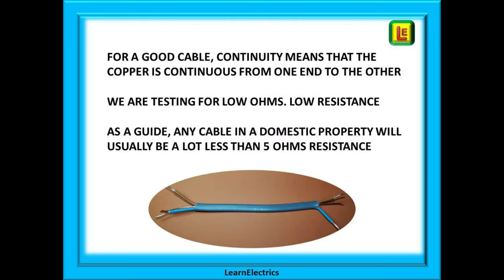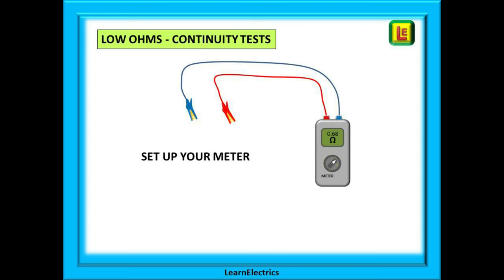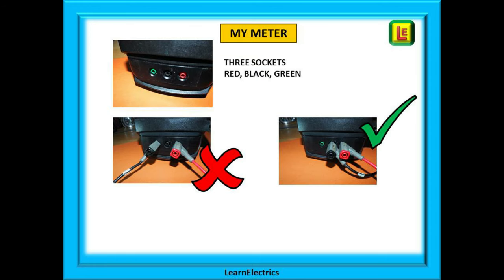For a good cable, continuity means that the copper is continuous from one end to the other. We are testing for low ohms, low resistance, and as a guide any cable in a domestic property will usually be a lot less than 5 ohms in resistance. The first step, always before doing any testing, is to set up your test meter and to make sure that it is functioning correctly. Different manufacturers make their meters with slight differences, but if you learn how to set up your own meter correctly then it is very easy to adjust to someone else's meter.